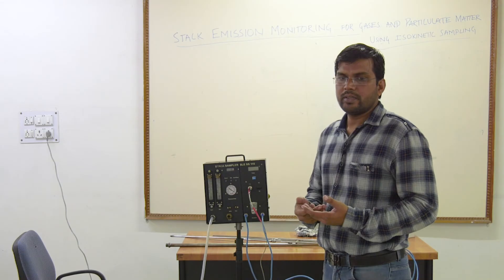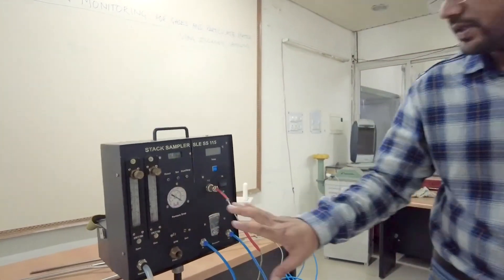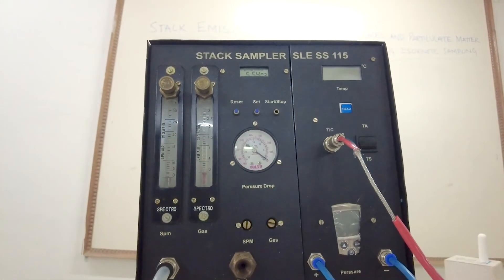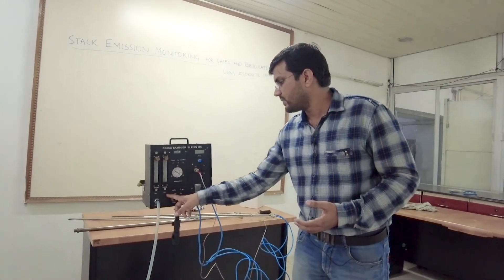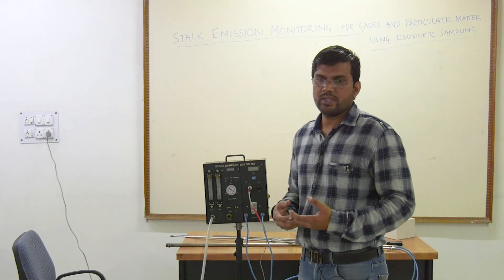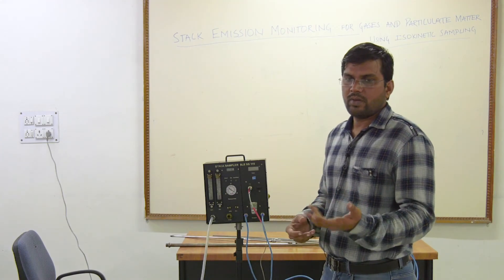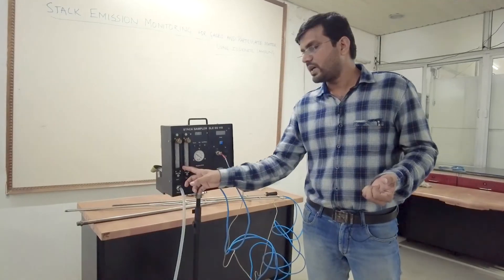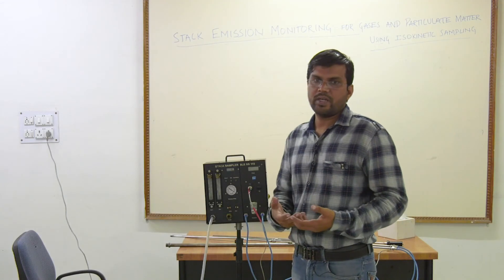To maintain isokinetic sampling, we use rotameters. This device has two rotameters — one corresponding to SPM and one corresponding to gas. When sampling for SPM or suspended particulate matter we maintain the flow rate through one rotameter; when measuring gases only we control the flow rate through the other. By measuring velocity through the pitot tube, we can calculate the flow rate, and by regulating that flow rate through the suction pump and rotameters we maintain constant velocity, ensuring the isokinetic condition of sampling.